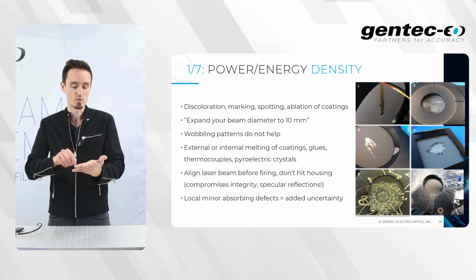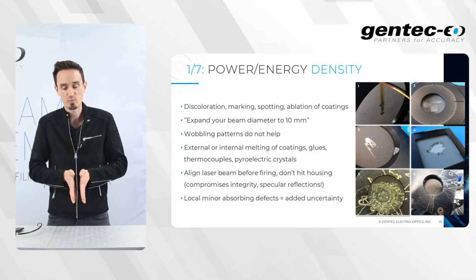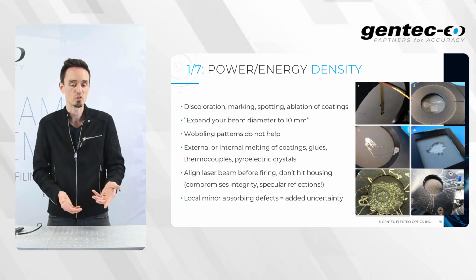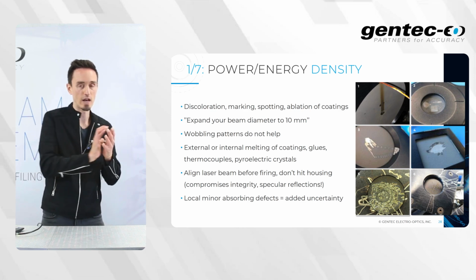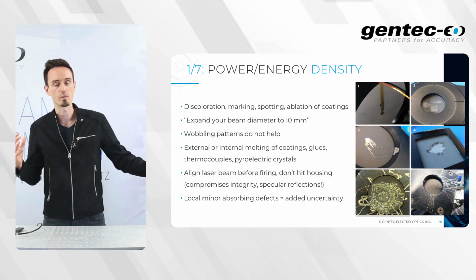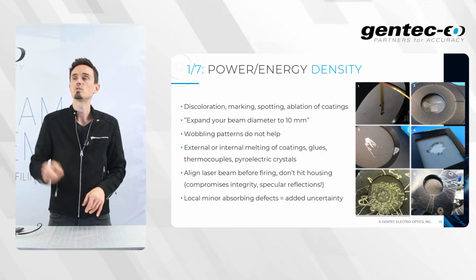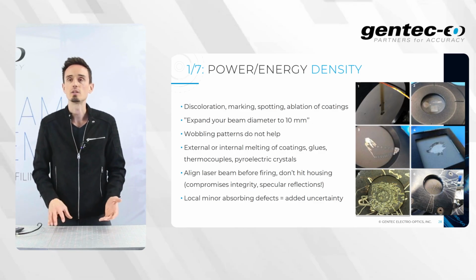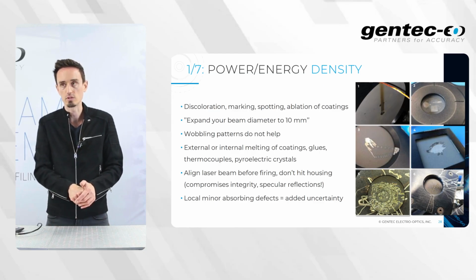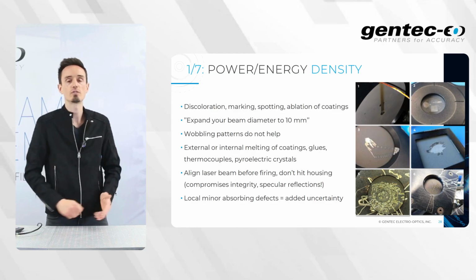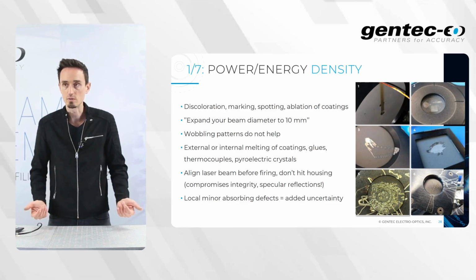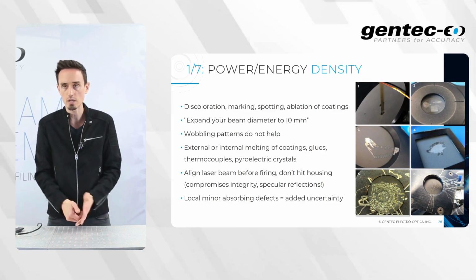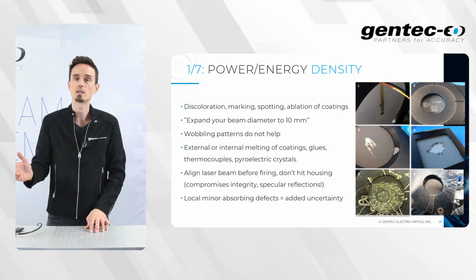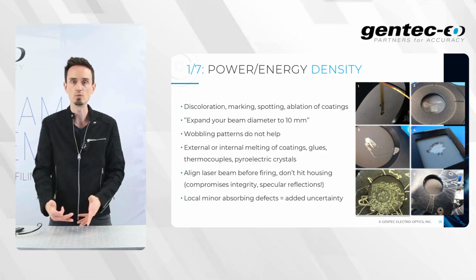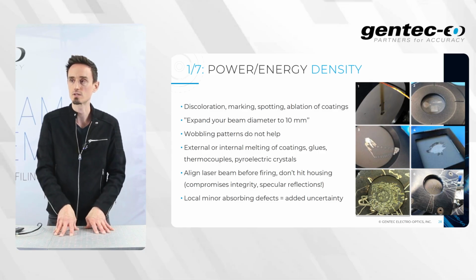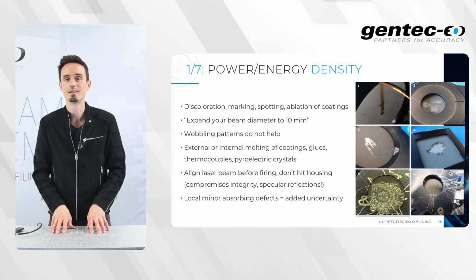It is not a matter of drawing a given shape, it is a matter of expanding the beam spot size, using a defocusing lens or the natural divergence of the beam, placing the detector further away from the source. The wobbling patterns that you could see on picture 3 usually do not help because the energy density level is just the same. It is not going fast enough, the dwell time is not that small to help potentially decrease the received energy locally. This is all resulting in external or internal melting of coatings, glues, thermocouples, pyroelectric crystals, some pretty bad damages here.